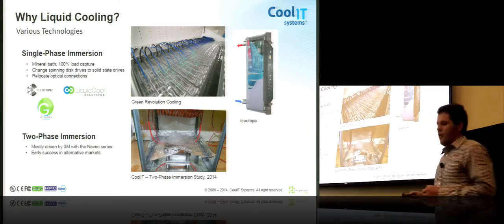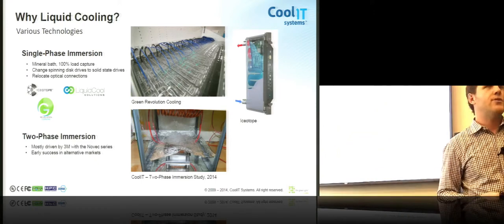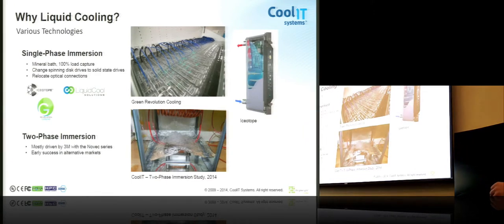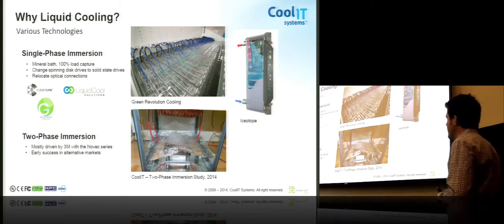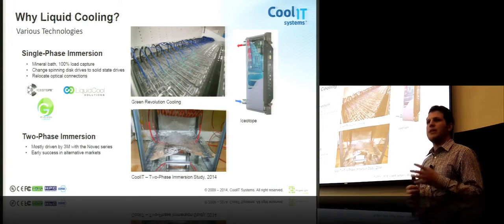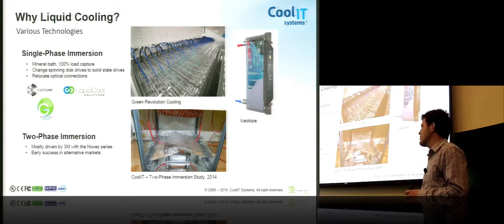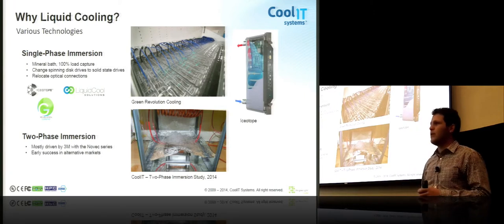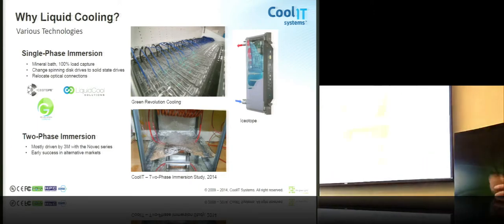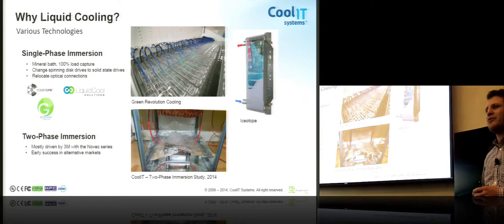So the next technology has really got a lot of press through the last two years. I think it's a pretty sexy technology and that's immersion. It has the major benefit, of course, of capturing 100% of the load. So this is known as mineral bath. In this scenario, you would have to change your spinning disks to solid state drives and you need to relocate any optical connections to outside the water. Of course, the groups that work in this area have got that mostly cased.